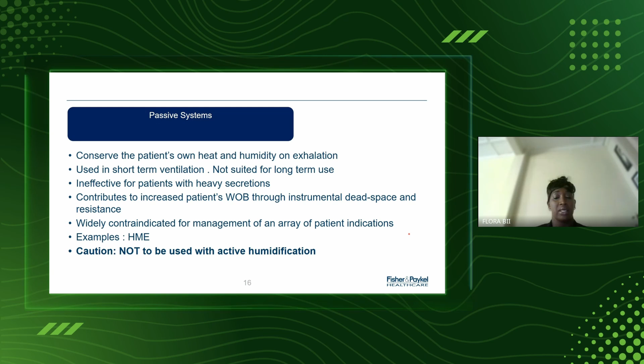It's also very important that I mention at this point that if you're using an active humidifier, which I will go to in a very short while, you are not supposed to use a HME with active humidification. Some of the hospitals that I have been to all across sub-Saharan Africa, many of them still use a HME together with the active humidifier, and I will show you why this would be a caution for you to be able to look at.